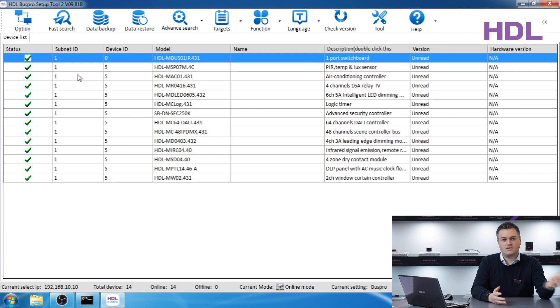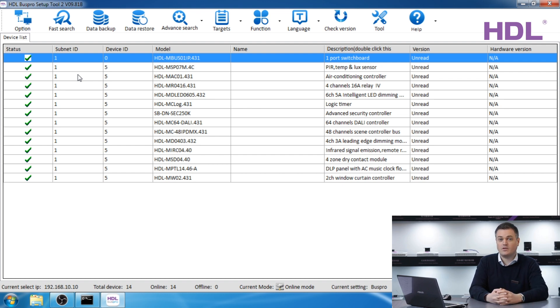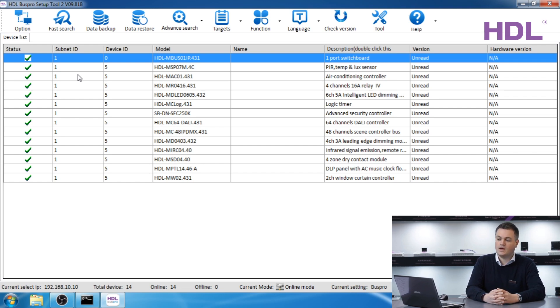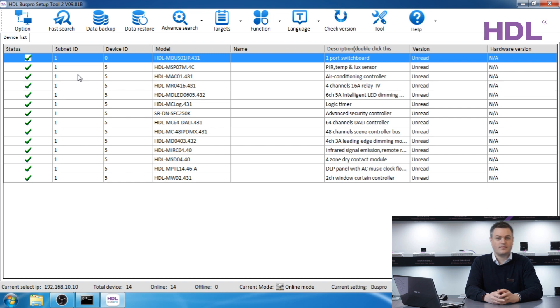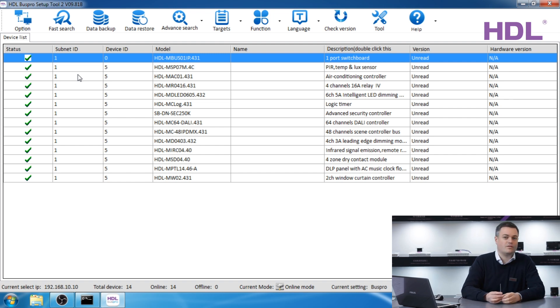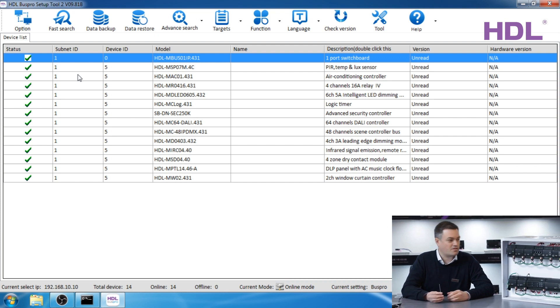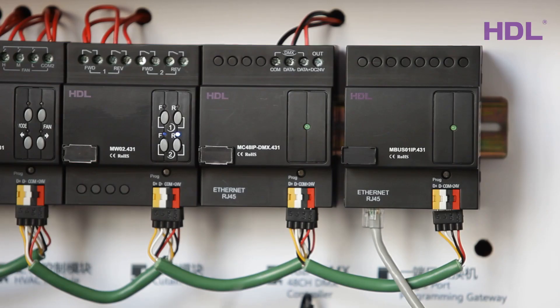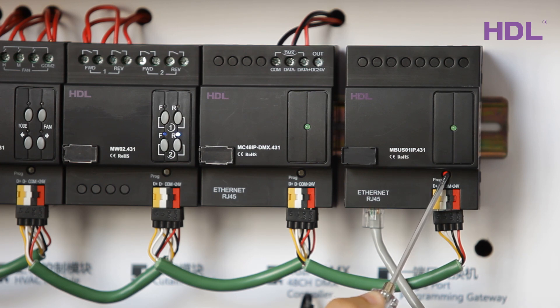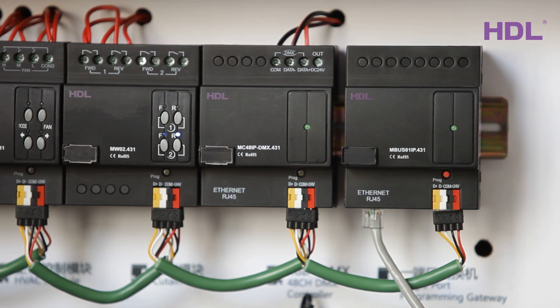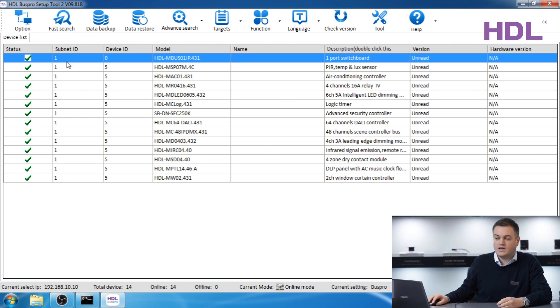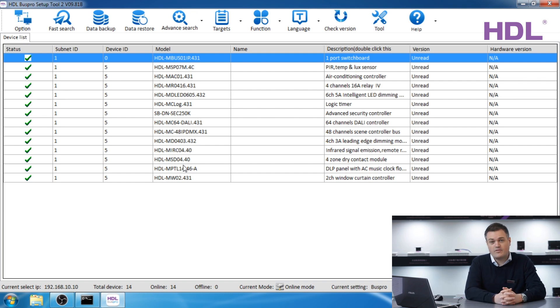If when you press fast search no devices show on the screen then there's probably a communication issue between your PC and the IP gateway. For example maybe you have an incorrect IP address, maybe they have a network problem. So you can troubleshoot this by resetting the IP of the IP gateway to 192.168.10.250. To do that you must press the button on the IP gateway for 15 seconds, this button here. When you press this button for 15 seconds the IP address will reset. If when you press fast search you only get one device, the IP gateway and no other devices, this suggests you might have a problem on your HDL bus. So please check the cabling.